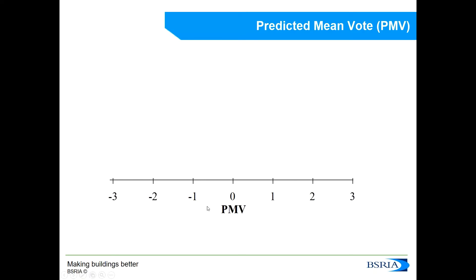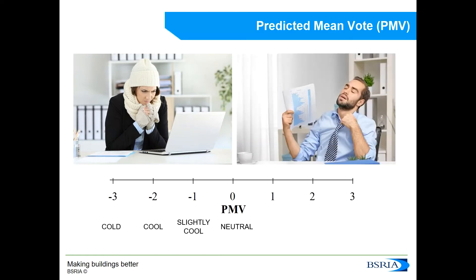To begin with the PMV, what we have here is the thermal sensation scale. The thermal sensation scale runs from minus three to plus three, in which zero means that a person would feel neutral with the environment. Minus one would mean they feel slightly cool, minus two that they feel cool, and minus three that they feel cold. On the other side of the scale, one, two, and three correspond to feeling slightly warm, warm, or hot. If we asked a lot of people how they feel in an environment and calculated the average, that would be the mean vote. The predicted aspect is because we do not ask people but predict how they are going to feel in advance.